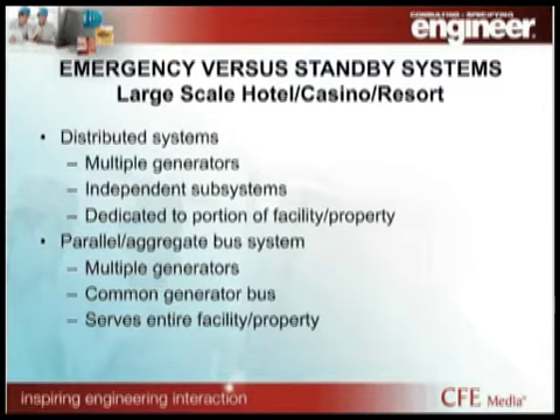It's easier for the operators to get their minds around a single generator and a group of transfer switches. Most operators are very comfortable with that. When we move into parallel, or what I like to call an aggregate bus system, it's typically comprised of multiple generators. You've got a common generator bus. We would typically segment that bus so you can isolate it from your load bus and also isolate it from itself, depending on how big the system is. And now you're really looking at a system that is global in nature. It serves the entire facility, the entire property.